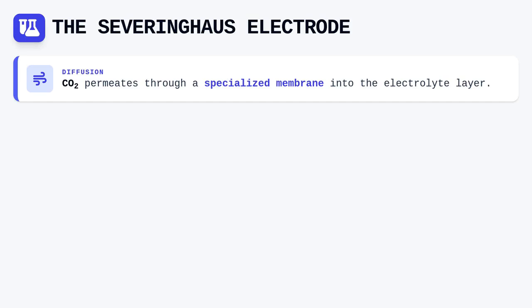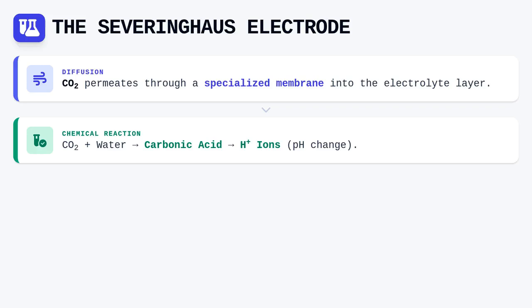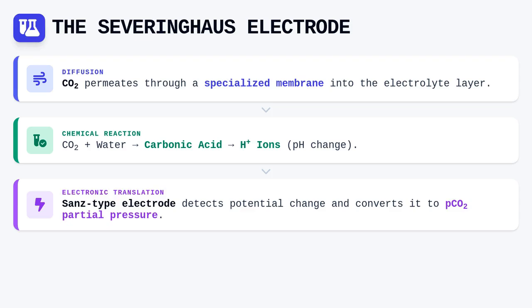The Severinghaus electrode represents a sophisticated evolution of the pH electrode, adapted for carbon dioxide measurement. It incorporates a Sanz-type glass electrode immersed in a bicarbonate buffer solution, separated from the blood sample by a CO2 permeable membrane. As carbon dioxide molecules diffuse through the membrane into the electrolyte layer, they react with water to form carbonic acid, which subsequently dissociates into hydrogen ions and bicarbonate. This local change in hydrogen ion concentration alters the potential across the glass electrode, which the system electronically translates into the partial pressure of carbon dioxide.